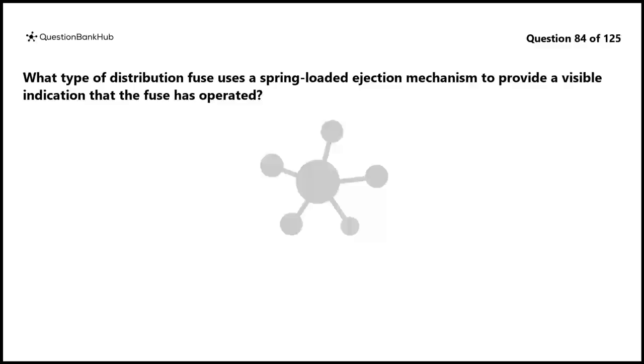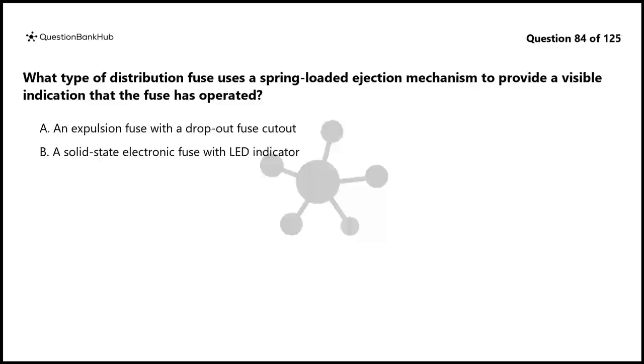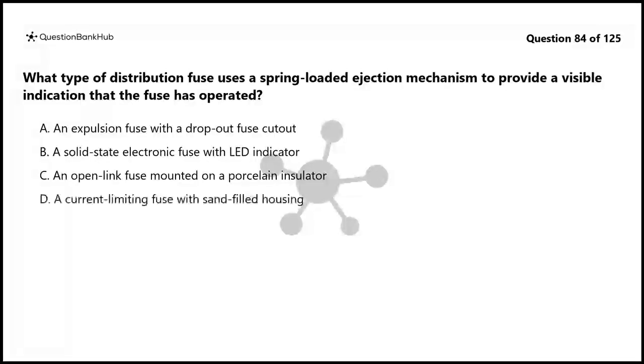Question 84. What type of distribution fuse uses a spring-loaded ejection mechanism to provide a visible indication that the fuse has operated? A. An expulsion fuse with a dropout fuse cutout. B. A solid-state electronic fuse with LED indicator. C. An open-link fuse mounted on a porcelain insulator. D. A current-limiting fuse with sand-filled housing.